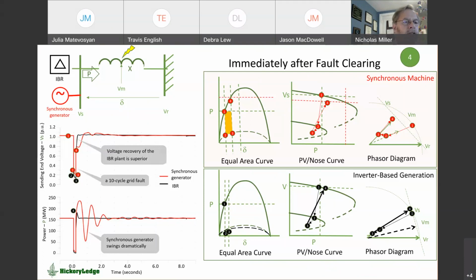end. In comparison, the inverter-based resource didn't swing out as much. So the angle is very different at 0.4 for the inverter-based resource than it is for the synchronous machine. So everybody, this is one of the things that inertia does for or to you. The synchronous machine has inertia. In this case, the inertia of the synchronous machine is not necessarily doing you a favor, because the machine has accelerated and it is now pulled out, and it must get rid of its extra megawatts during the resynchronization as it moves up the power angle curve, or it will slip a pole.